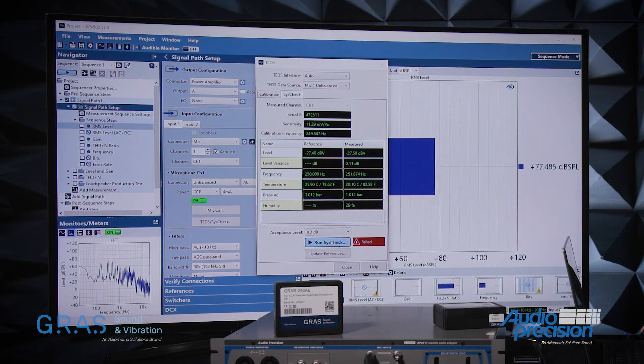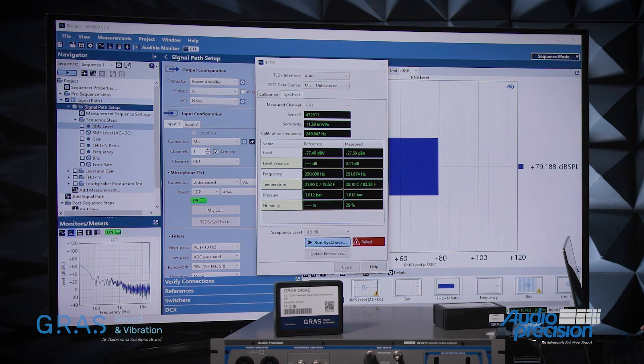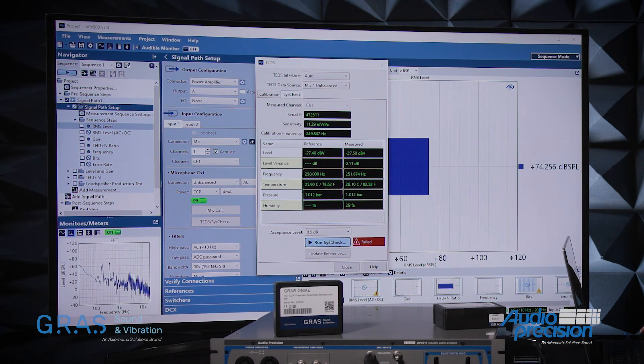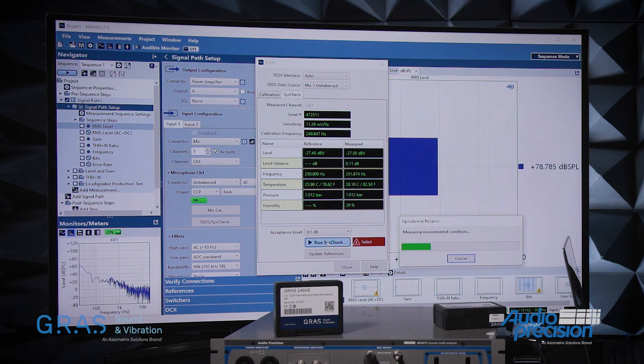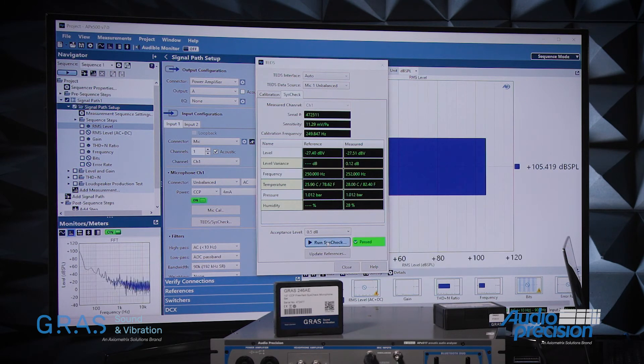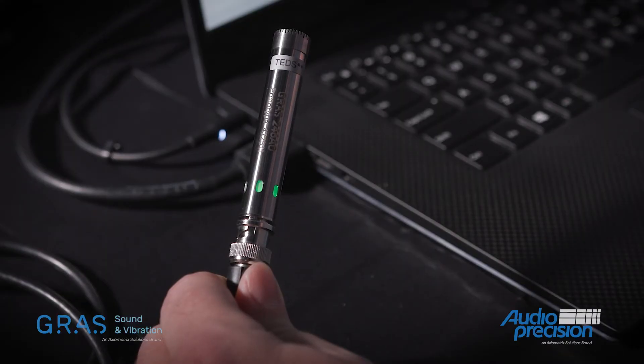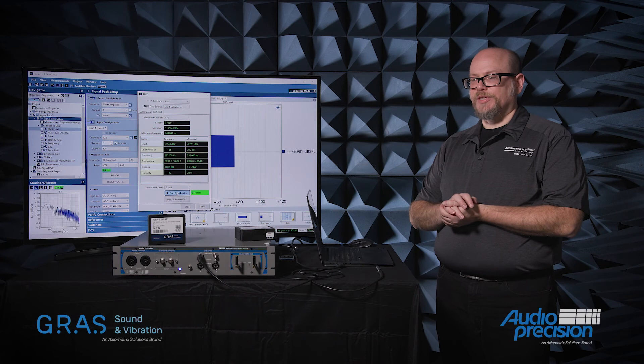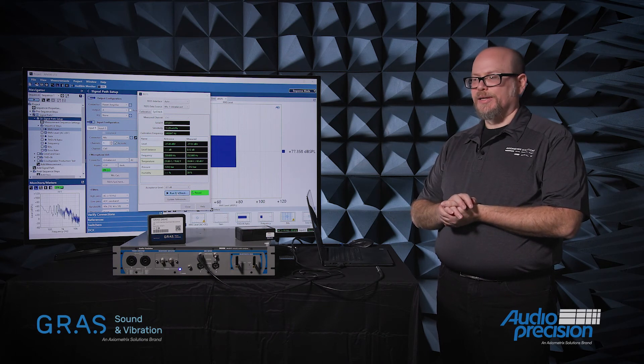Perhaps in this measurement setup I'm prepared to accept a little bit higher deviation, so I'll set my threshold to be 0.5 dB. I can run SysCheck again. And now it has calculated that this microphone is, in fact, operating within 0.5 dB of its design, or last calibrated sensitivity.